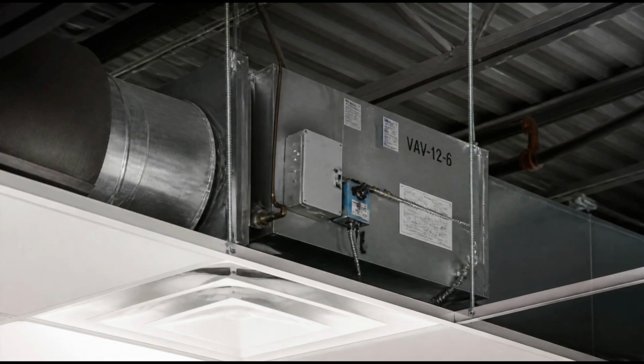When a building may be largely unoccupied, some level of ventilation is typically maintained. The building's air is not left to grow stagnant. A small but steady introduction of outside air ensures that when people return in the morning, the indoor environment is fresh and ready. The system may send part of the air back through the air handler. The recirculated portion of the return air joins the fresh outside air and enters the air handler together. There, the blend is filtered and conditioned as one. The coils adjust the temperature, the fans maintain the pressure, and the combined air, now cleaned and brought to the desired conditions, is ready to begin the supply journey once again.